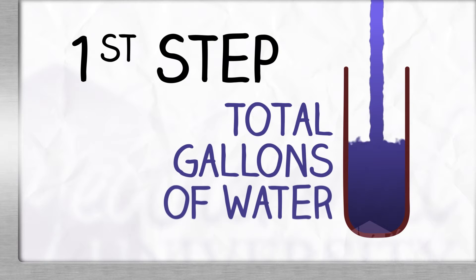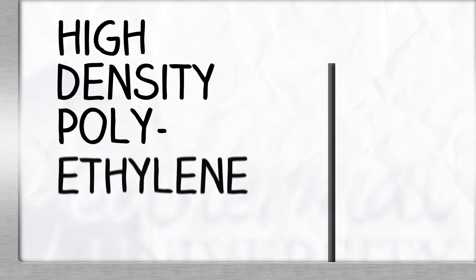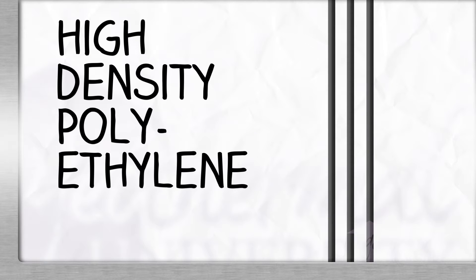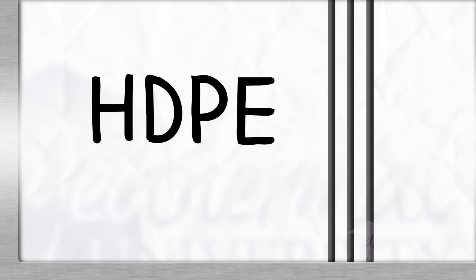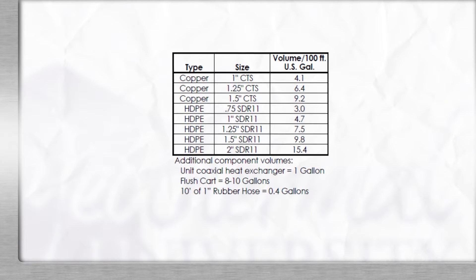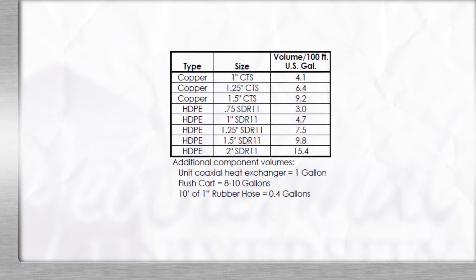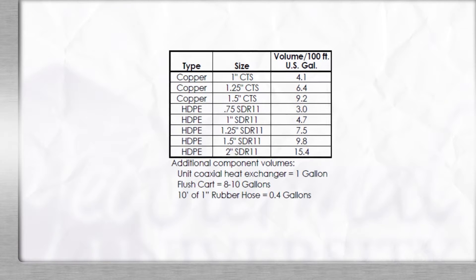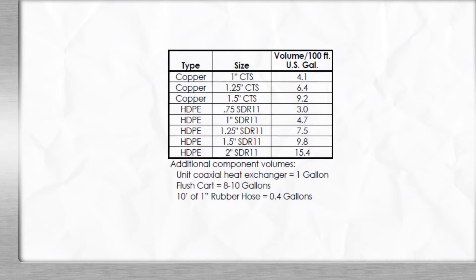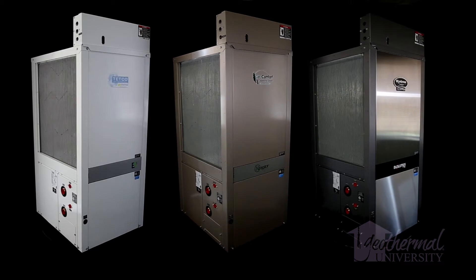Our first step is to calculate the total gallons of water for the entire system. In our example, we are using high density polyethylene pipe, or as it is abbreviated, HDPE. You'll need to have handy a copy of the pipe fluid volume chart in the Geothermal Unit Installation Operation Manual, or IOM. A copy of a typical IOM is attached to this video. In our example, we'll use a three-ton system.